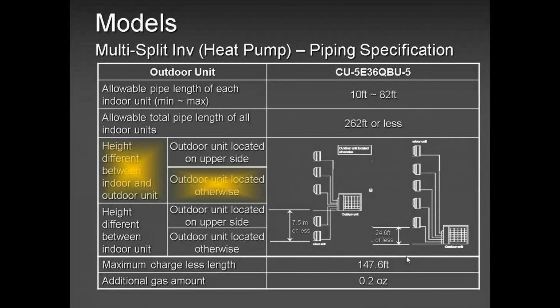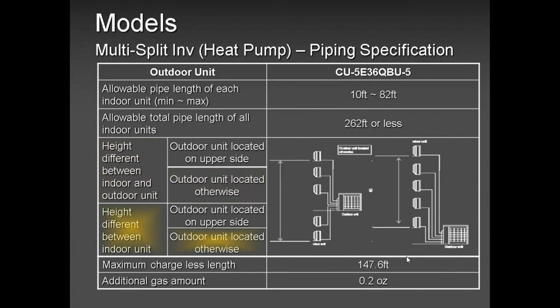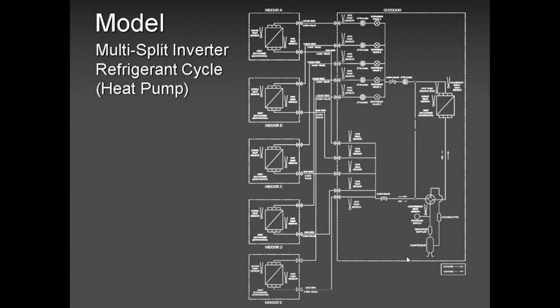That's your height difference they're talking about. In this case, 49 feet is the height between indoor and outdoor unit, and when the outdoor unit is on the upper side, you need to maintain at least 49 feet and below. The height between indoor units, from the last one, which is the bottommost, to the topmost, is 22.6 feet.